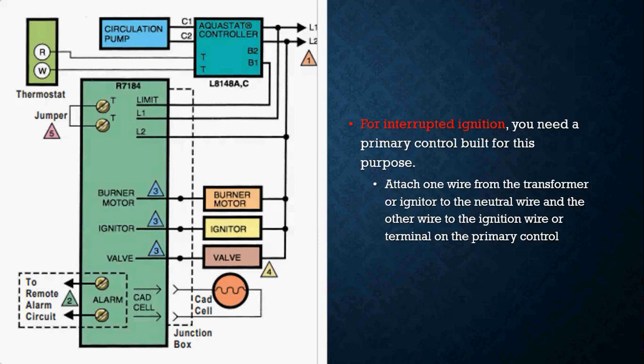If you're going to do interrupted ignition, attach one wire from the transformer. You have to obviously make sure that you have a primary control that is built for this purpose. You are going to attach one wire from the transformer or igniter to the neutral wire and the other wire to the ignition wire or terminal on the primary control.